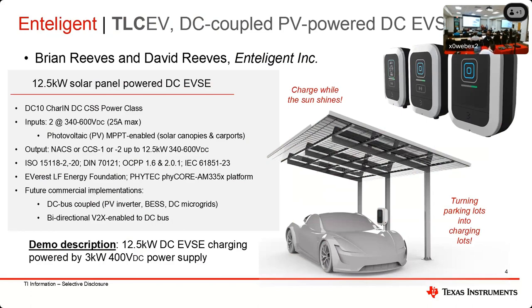One of our initial thoughts, but what we're working on with some of our partners, is hybrid photovoltaic inverters, and they're able to have different energy sources contribute to an internal 400-volt DC bus. So you would have photovoltaic coming from the roof and into a set of buck boost converters from each PV string, and they boost or buck up to 400 volts to energize that 400-volt line. That 400-volt line ultimately feeds into the AC-to-DC converter, which will take that DC, convert it to AC 240 or 120, depending on what output is needed, and then put it to the house load or ultimately to the grid.